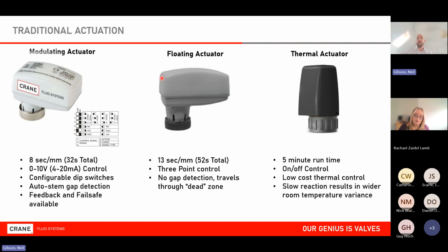So some typical examples of the actuators we tend to come across in the market today. You've got a modulating actuator on your left-hand side. That can be fairly quick acting, 8 seconds per millimeter. It's a 4mm stroke, so we can close it in half a minute. Can control on a 0 to 10, a 4 to 20 milliamp. But configurable dip switches, again, physical dip switches. I have to open up that actuator to change a dip switch, i.e. from direct to reverse, linear to equal percentage, 0 to 10 to 5, 0 to 5, etc. It may have some form of gap detection built within there, and it can be configured with feedback and fail-safe.